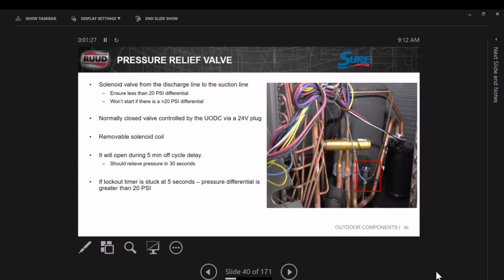So looking at the pressure relief valve we talked about earlier around the compressor, it's mounted here. Okay, and it ensures that there is less than 20 psi differential across the compressor suction and discharge, or the unit won't start if it's greater than 20 psi. It's a normally closed valve controlled by the outdoor control board, and it has a 24 volt plug that goes to it. It's just a regular 24 volt solenoid. It's a removable coil. It can be replaced. It will open during a 5-minute off delay. So in other words, it will open up and relieve the pressure for about 30 seconds.